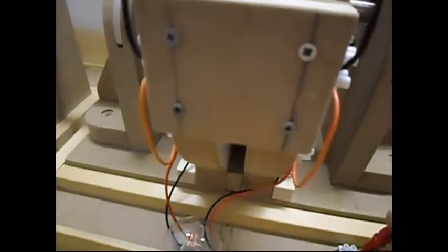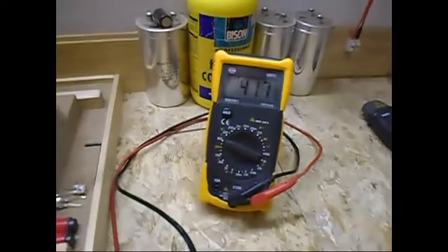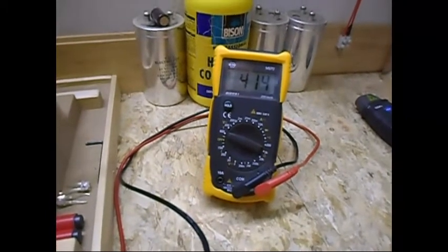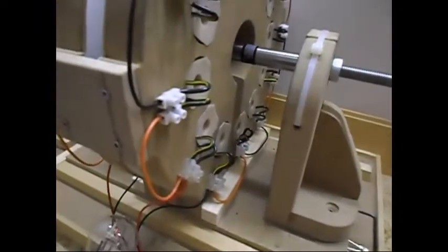And what is the voltage now? For the ones I want to know also. I'm sitting now at 415 volts. That's pretty good actually. It's around 100 volt drop. Something like that.